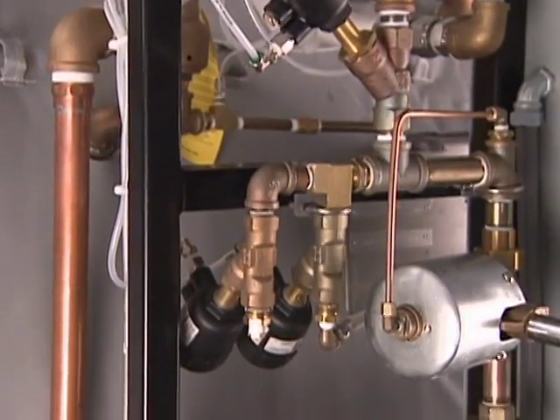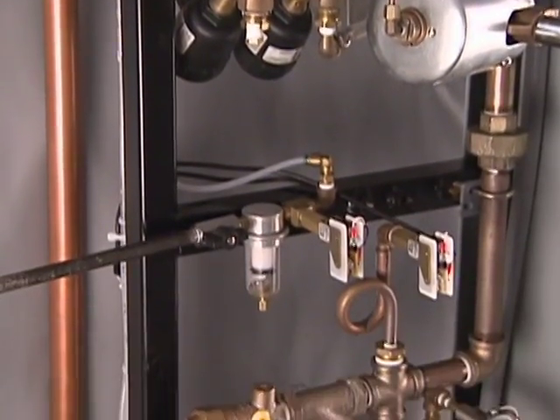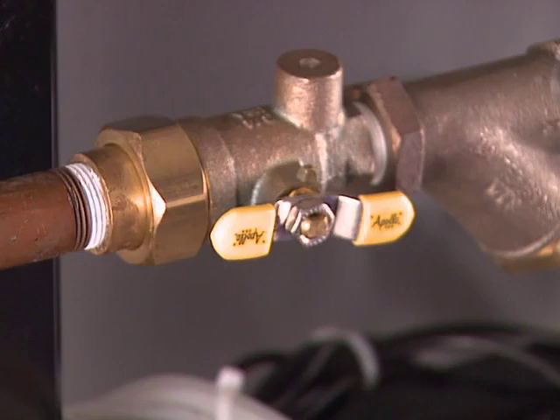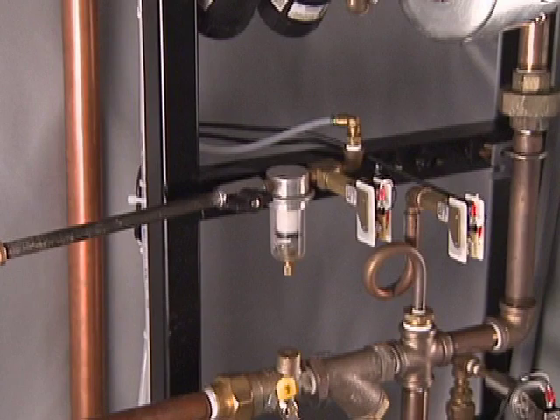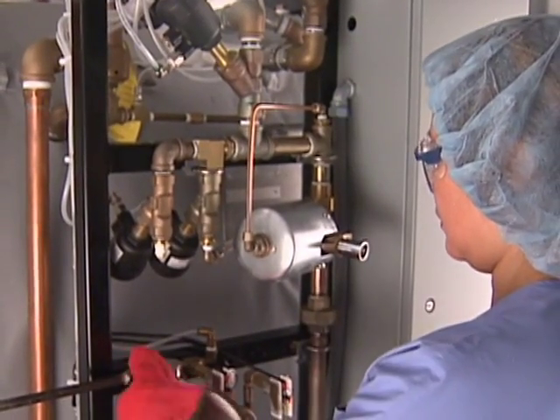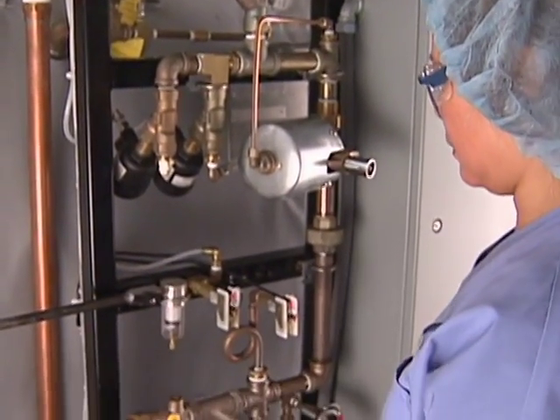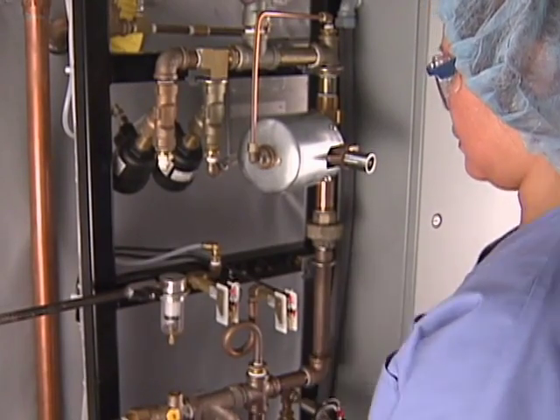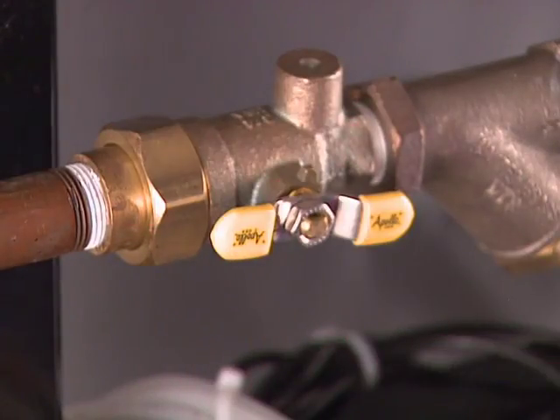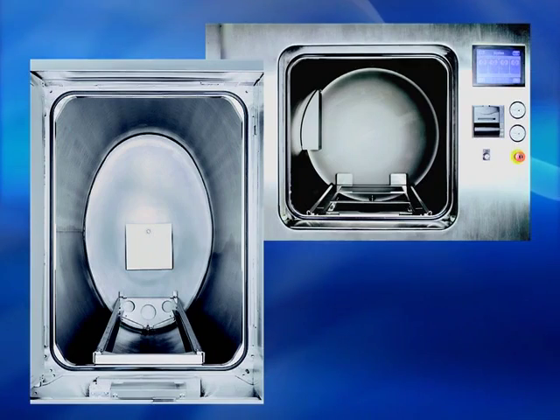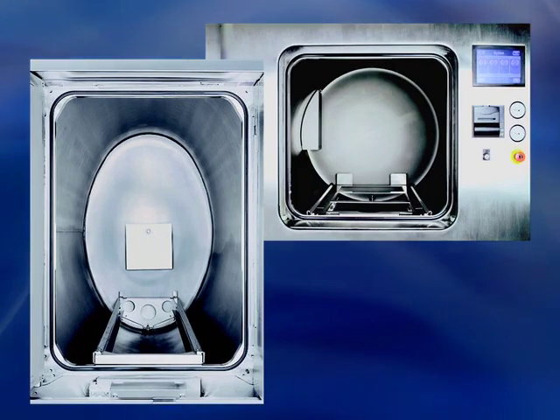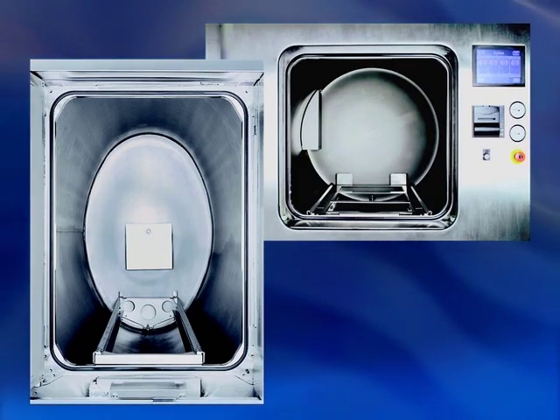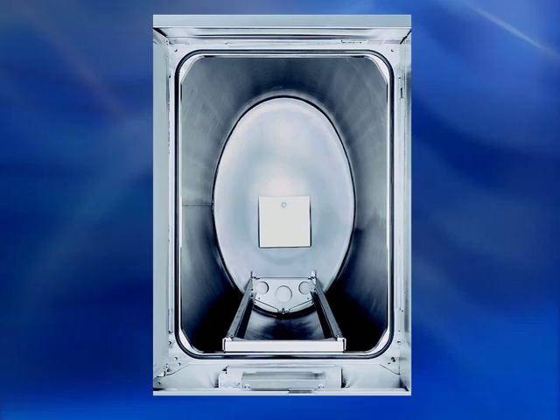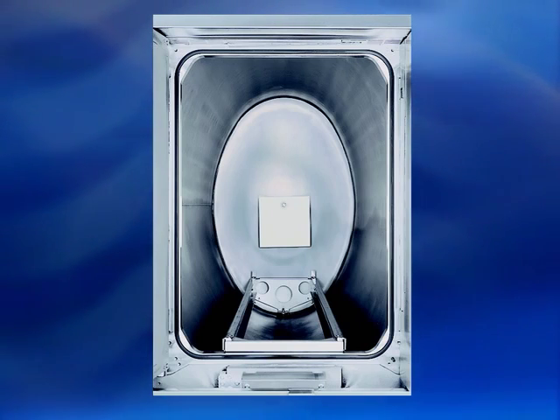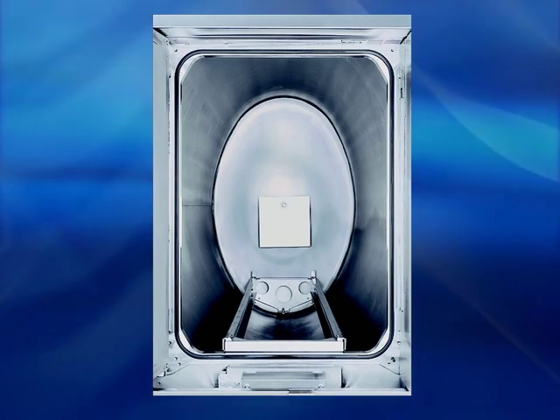The piping skid is located in the sterilizer service area to the left or right of the chamber. You'll also find the steam, water, and air supply valves located within the service area or behind the side access panel if the unit is cabinet enclosed. Each of these valves should be in the open position before you operate the sterilizer. Evolution's unique elliptical and round chambers promote even pressure and heat distribution within the chamber. The 26-inch wide chamber facilitates easy loading, accommodates wide instrument sets, and processes each load with minimal steam consumption.